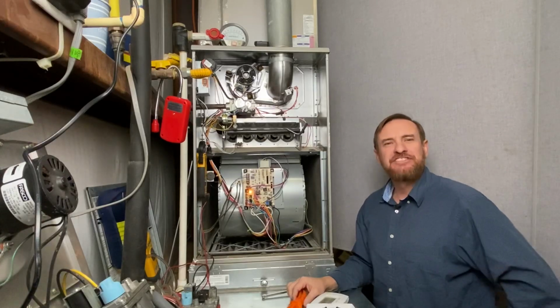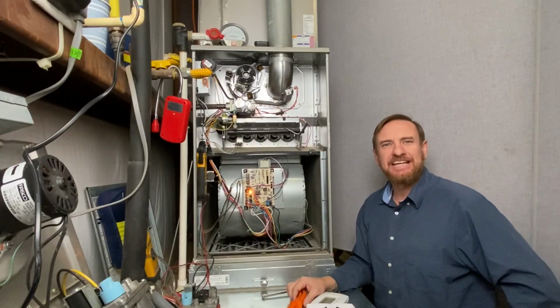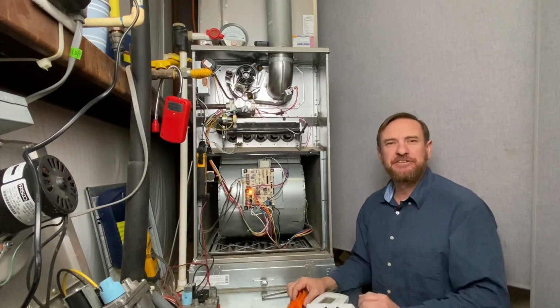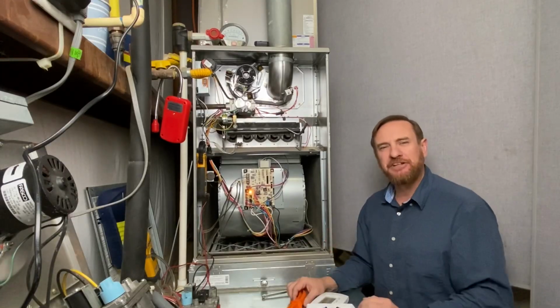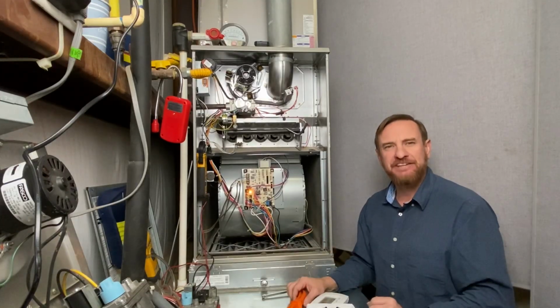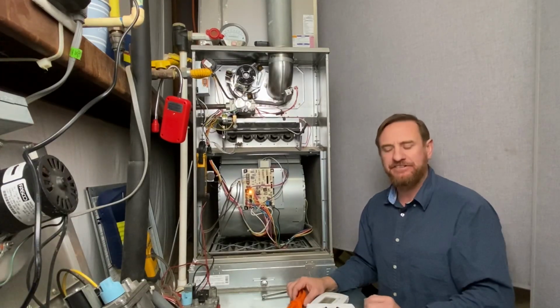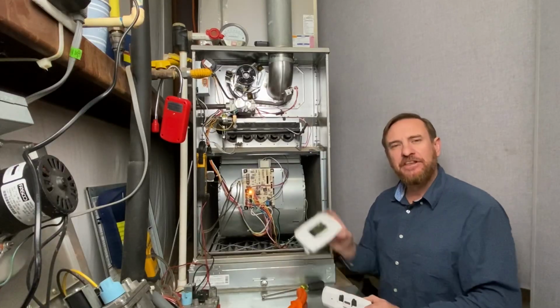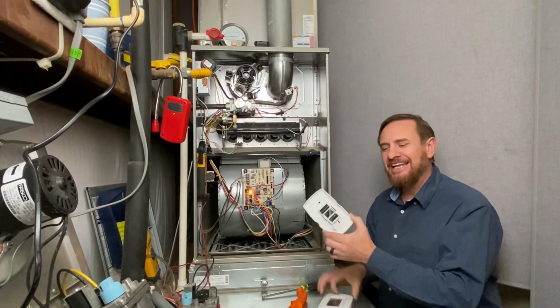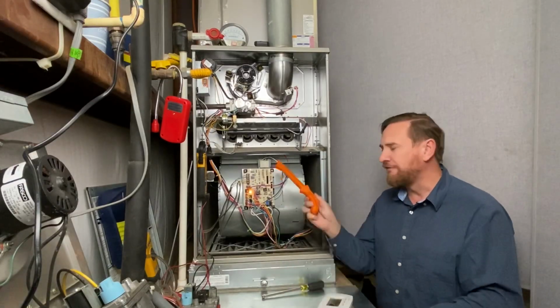Today we're going to cover the sequence of operation for an 80% gas furnace. This is very similar to several other models, but I'm going to focus specifically on this one. I'm going to roll through it pretty fast at first, then we'll go through and break down all the steps. So to get started, the thermostat calls for heat, connecting R and W, sending 24 volts to the IFC.